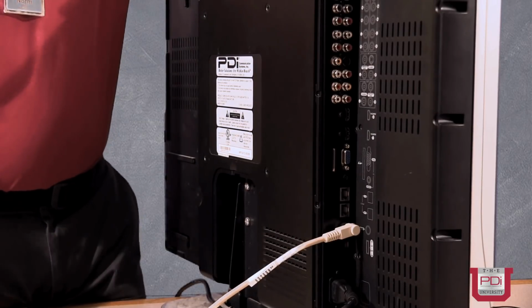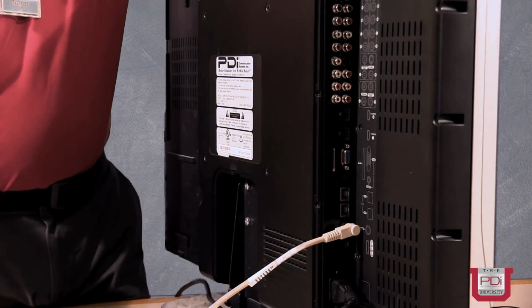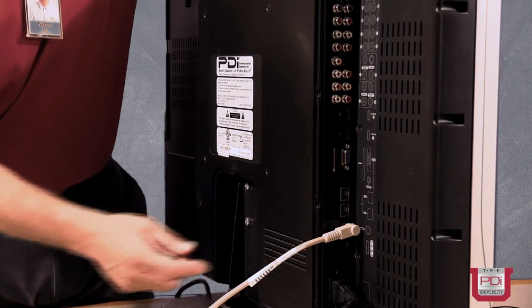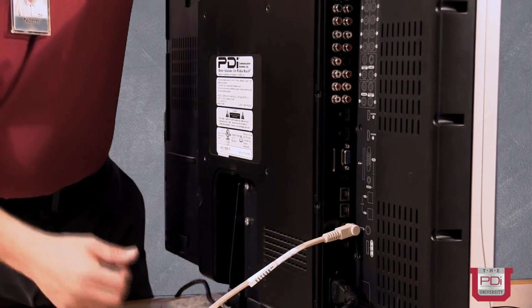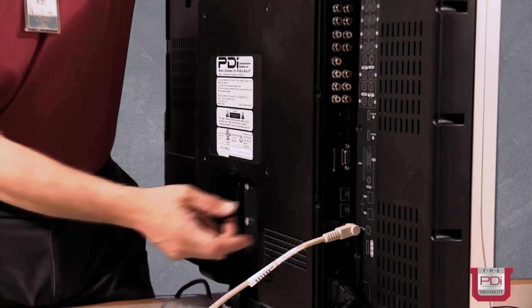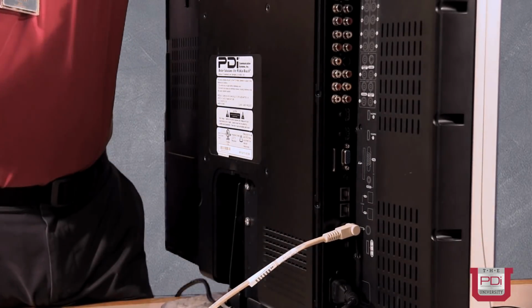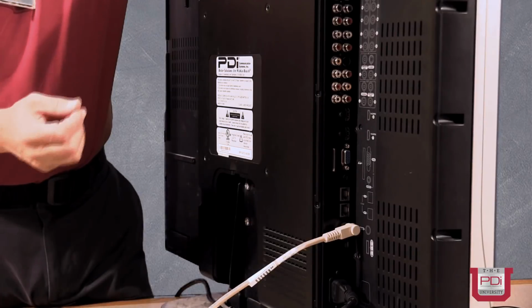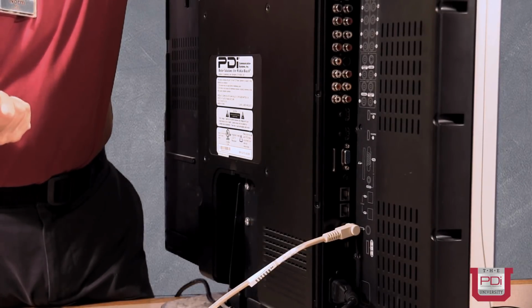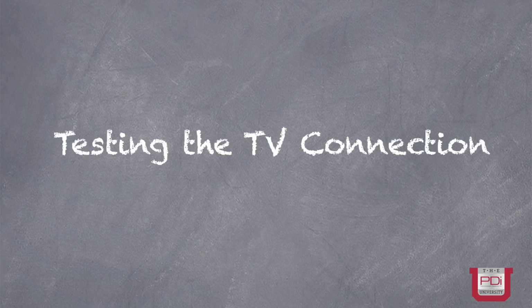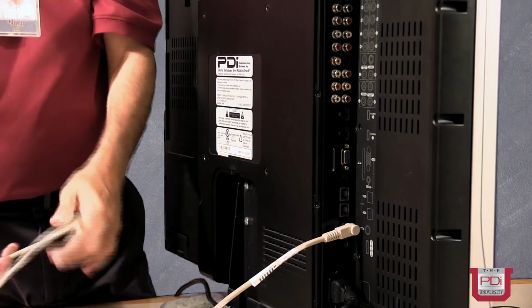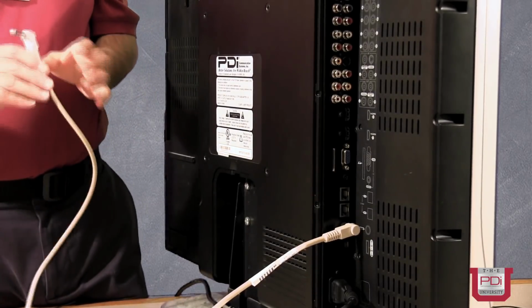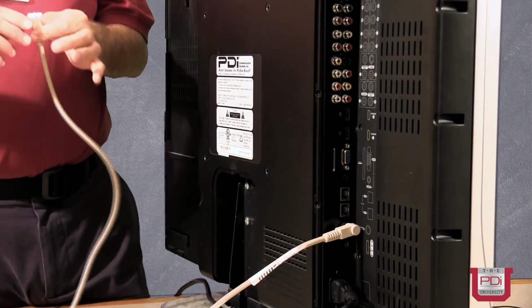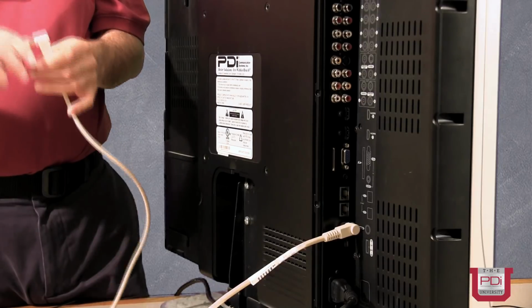Usually what I recommend is that you connect everything up, including the pillow speaker, turn the TV on, and then start operating the pillow speaker and look for some response from the TV. If it's not working, then you need to slide the switch to another position and try it again. A second way to troubleshoot a control issue with a pillow speaker is to simply disconnect the jumper cable at the wall plate, leaving the cable still connected to the TV itself.